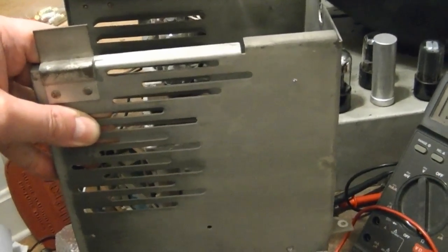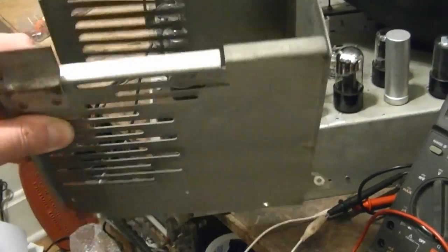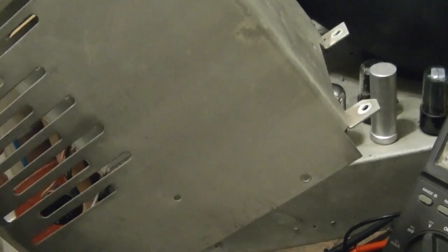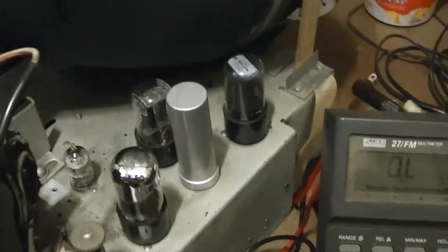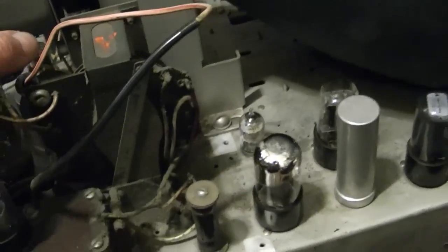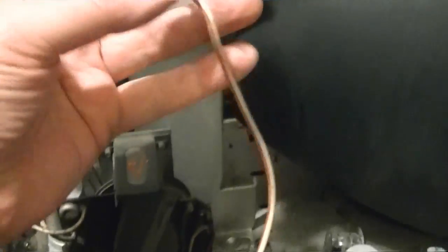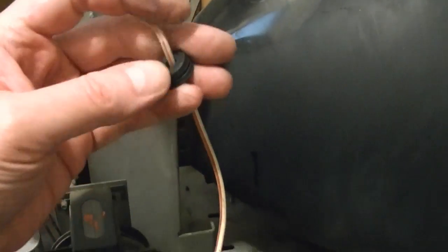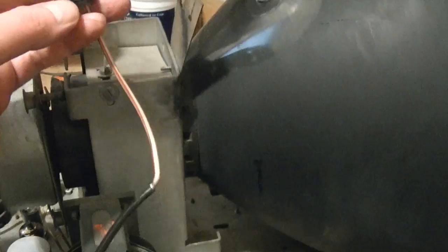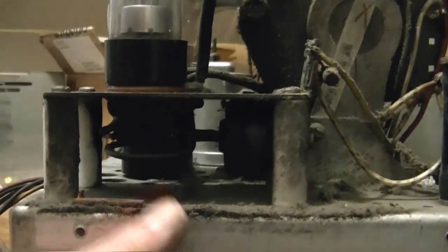Something else I want to take a closer look at is inside the high voltage cage. Fairly easy to take these off - remove a few quarter inch screws and carefully slide the bushing out. It fits in a notch in the high voltage cover, and there you go. I want to clean out all this dust, especially down in here. You're going to get arcing from all that dust and debris that accumulates.